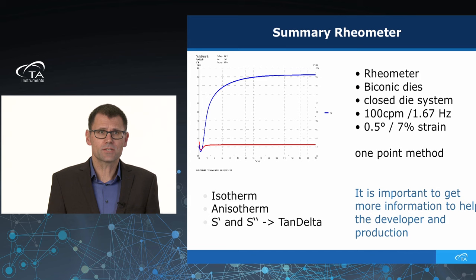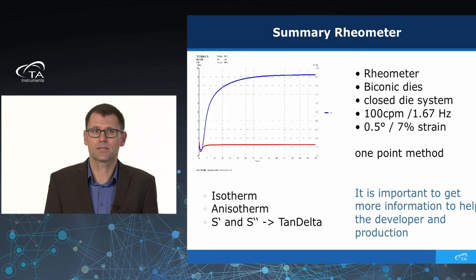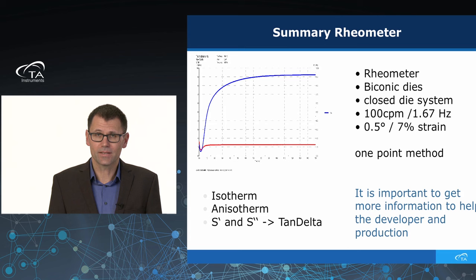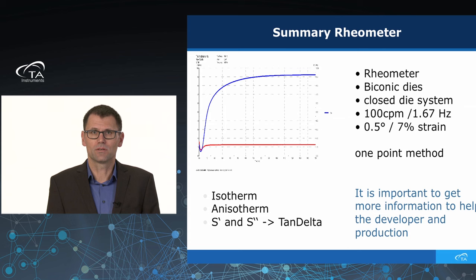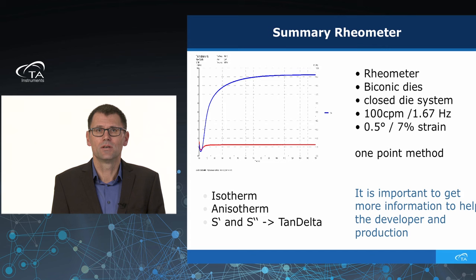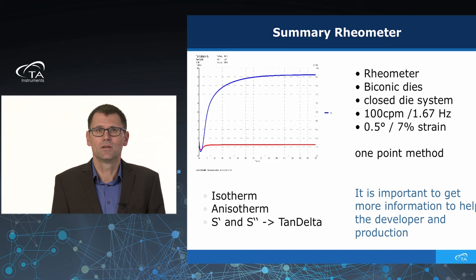A short summary for the MDR rheometer: what is typical on the market — a bi-conic die, a closed die system, fixed frequency at 100 CPM (1.67 Hz), at 0.5 degree of strain, about 7% strain. Again, like the Mooney, we are measuring only at one shear rate. During production we encounter the whole range of shear rates, but we characterize our material with only a one-point method. That is why we really need more information for developers and production teams to determine whether materials are suitable for production.